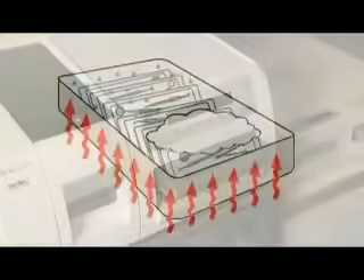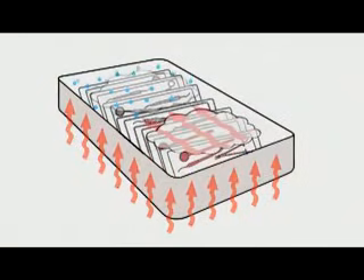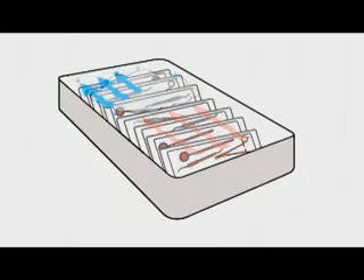The STATIM 7000 uses superheated steam to dry instrument pouches. The thermal energy, or heat, is extracted from the steam and is transferred directly to the instruments, quickly evaporating any residual moisture. The 7000 boasts industry-leading drying in as little as 12 minutes.